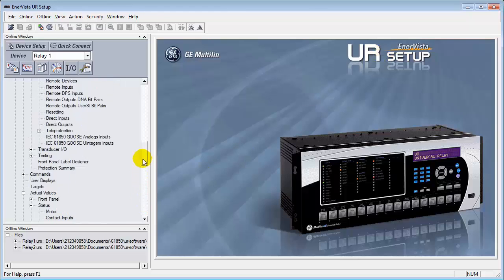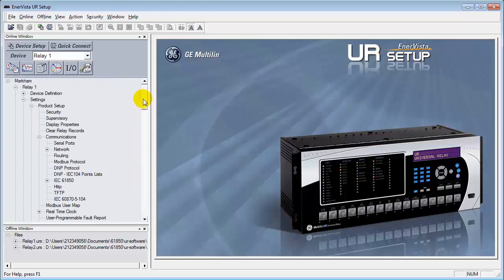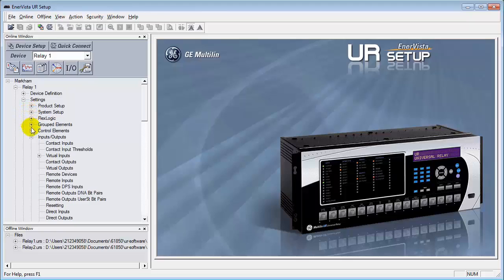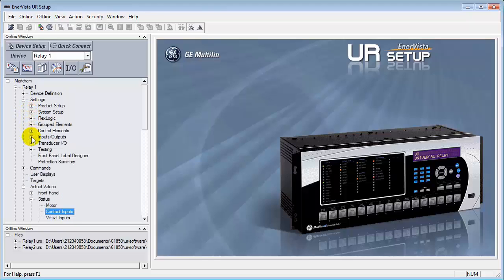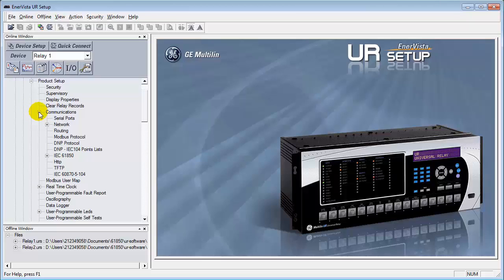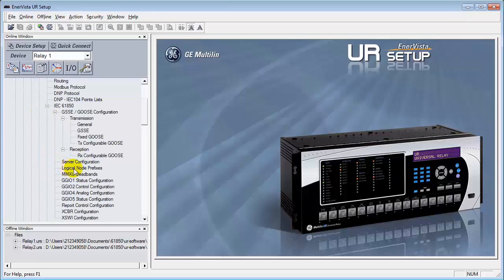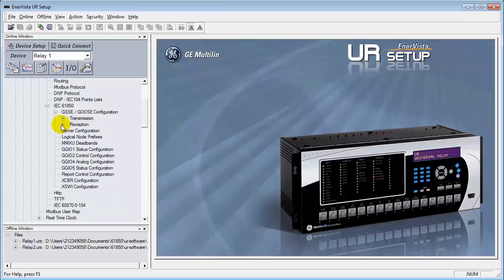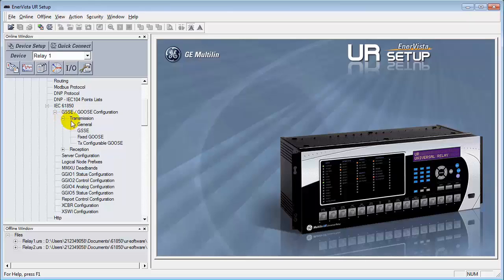Now, from the publishing point of view, there's a couple of things that we need to do from the fixed goose side of this. First thing we're going to do is we need to go into product setup under settings. We need to get into the communication tab. And we're going to go down to IEC 61850. Under 61850, there is a transmission tab and a reception tab. We're going to focus first on the publisher side, which is going to deal with the transmission tab. We're going to open this up. We're going to look at a couple of things here. First of all, the general. What is this?